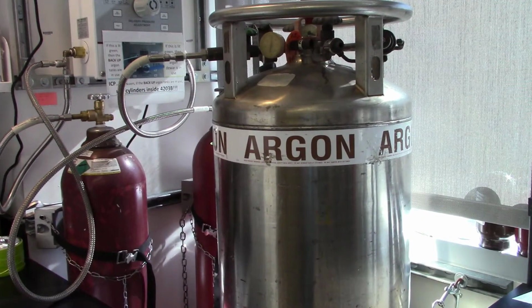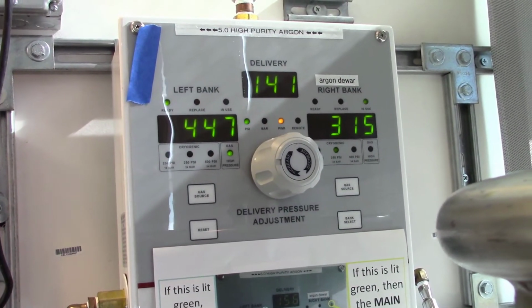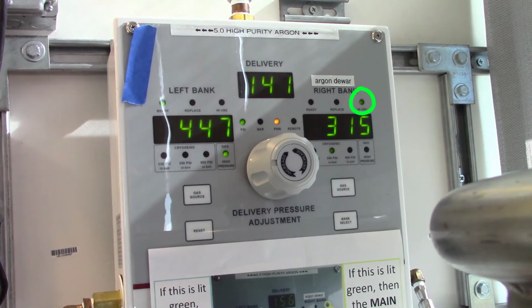Before you set up to run the ICP, it's important to check that the argon dewar is supplying gas to the system. To do this, look at the switchover station on the wall and check that the in-use light is green on the right bank. If it is, then it's okay to use the dewar. If this light is off and there is a red light that says replace, then speak with the staff contact before proceeding, because you'll need to use the backup cylinders located directly next to the instrument in the ICP lab.